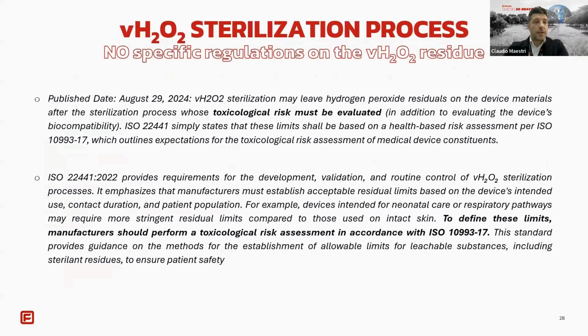Currently, there are no specific guidelines or regulations which fix a vH2O2 residue limit inside the product, but just, as we can see here, some general reference in ISO 22441. To define these limits, manufacturers should perform a toxicological risk assessment in accordance with ISO 10993-17.